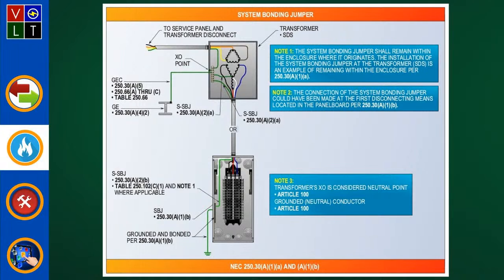All right, let me get back on this. So when I'm looking at this and I start sizing the system bonding jumper, we'll be looking at table 250.102C, note one. It's going to say this is based on the ungrounded phase conductors, up to 1100 kcmil copper and 1750 kcmil for aluminum.